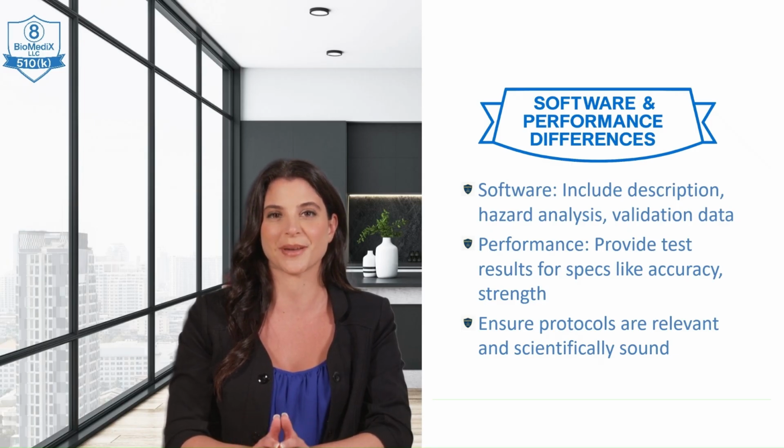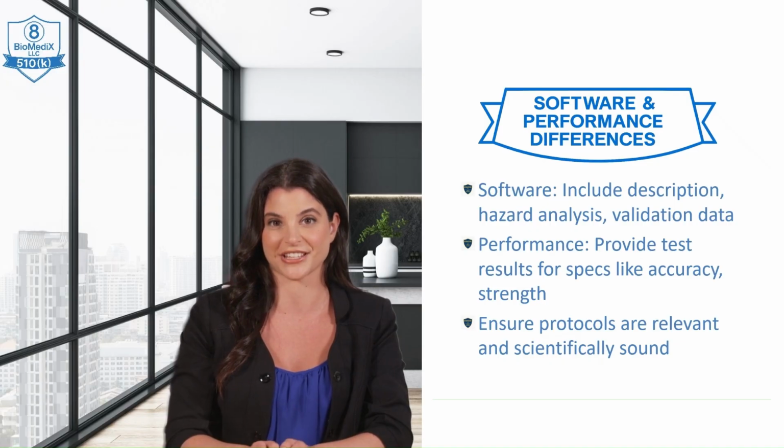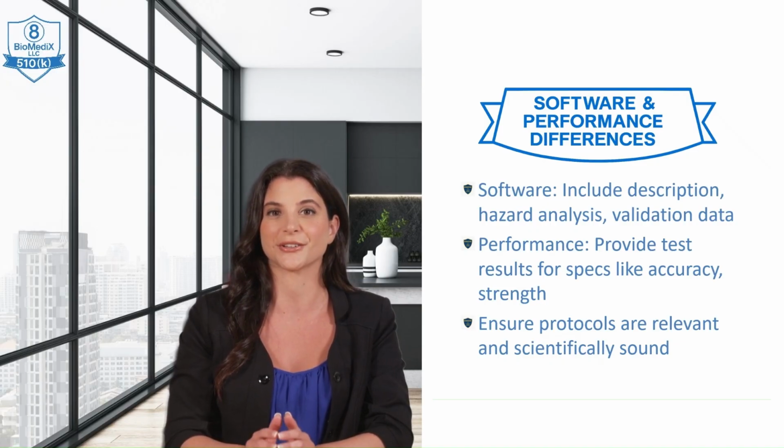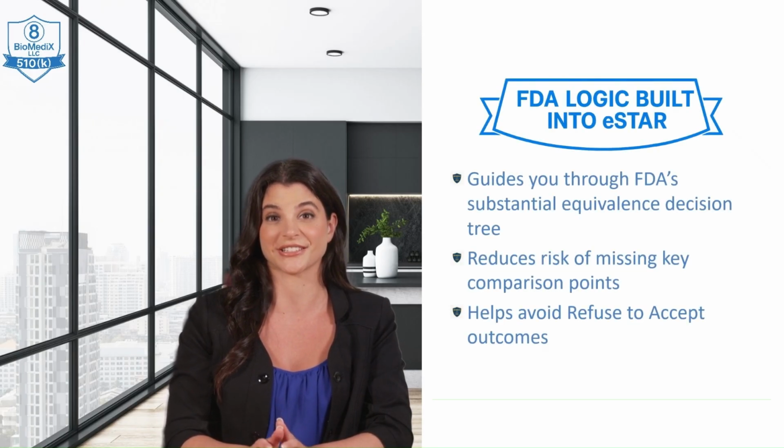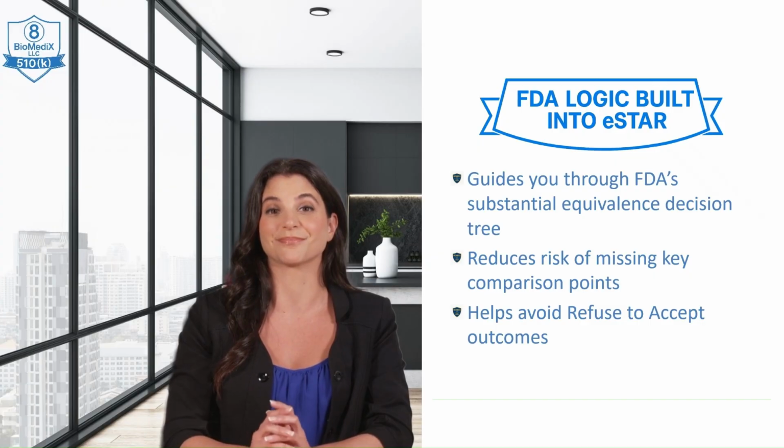eSTAR's structured format implicitly walks you through the FDA's substantial equivalence decision logic, ensuring you consider all relevant aspects like intended use, technological characteristics, and performance data. This helps ensure you don't miss a critical comparison point, which is a common reason for refuse to accept decisions.